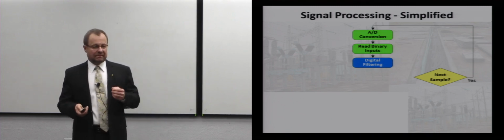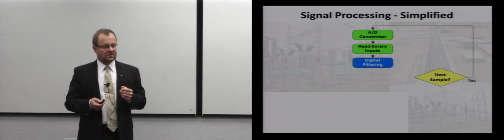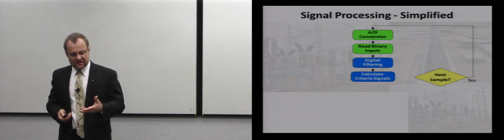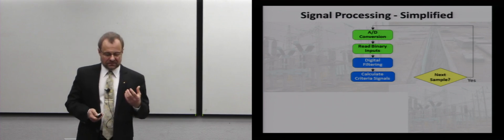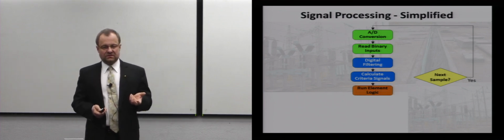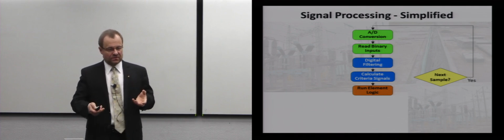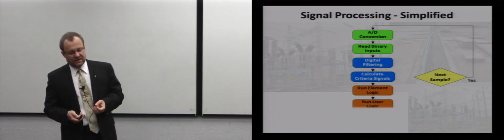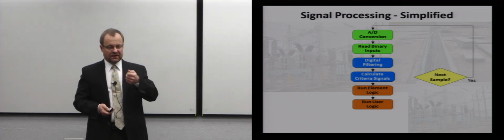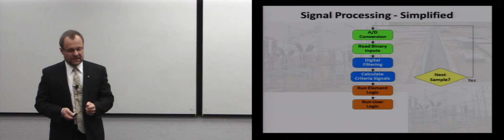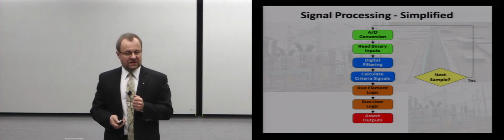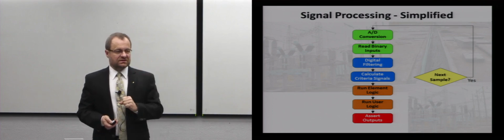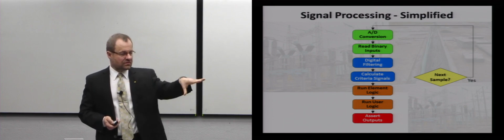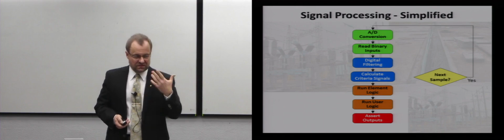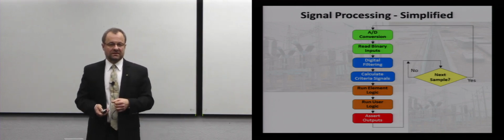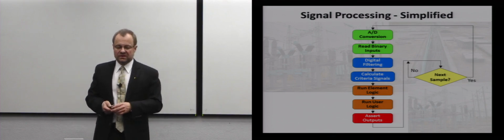I may want to calculate a power or an impedance or a magnitude from those input currents and voltages. Then I would like to run my criteria signals, magnitudes and so on. Then run the element logic. So if I'm a distance relay, I have to crunch some numbers in a specific way to be a distance relay, right? Then I run user logic. The user tells me, take this input, AND it with that, run this timer, and then close this output, right? So then I assert my outputs. Now, outputs are physical outputs, such as relays closing contacts. Or this is a communications-based output. I may send a message through an Ethernet port to tell somebody that something happened, but it's an output. And then I will wait for the next sample, right? That's the very generic, unified way you would build a digital relay.